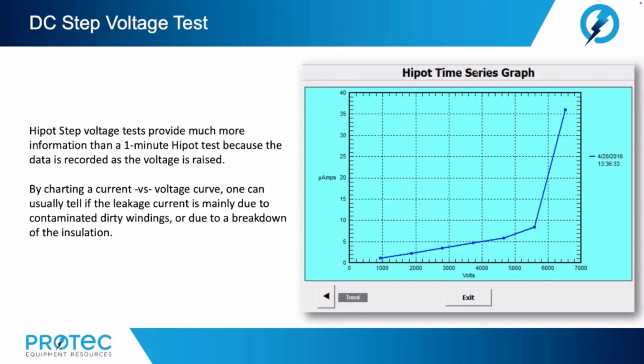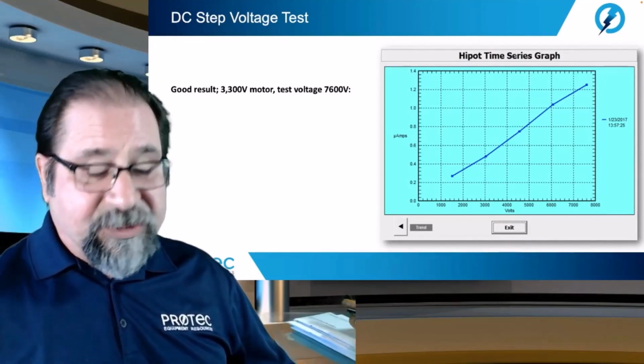Hipot step voltage tests provide much more information than a 1-minute hipot test because the data is recorded as the voltage is raised. By charting a current versus voltage curve, one can usually tell if the leakage current is mainly due to contaminated dirty windings or due to a breakdown of the insulation. So let's take a look at some test results.